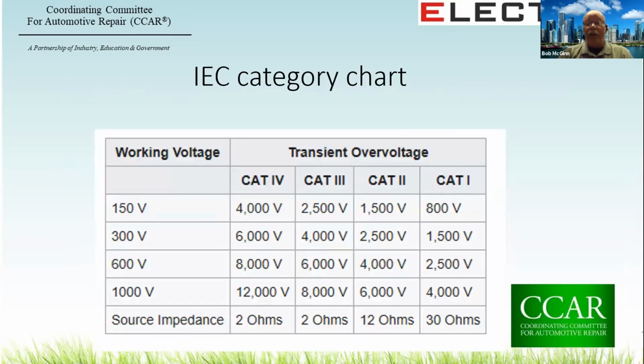Now, this chart is going to show you maximum transient protection for the working voltage range. Cat 3 600 being the minimum, devices afford you transient voltage protection up to 6,000 volts. You can go to Cat 3 or Cat 4 if you so choose. What I'm trying to convey here, simply being a Cat 2 at 600 volts is not going to provide you the before mentioned 6,000 volt transient, and as you drop in that category down to Cat 1, it reduces. It's about the transient, that if something happens, you will be protected reasonably against it.